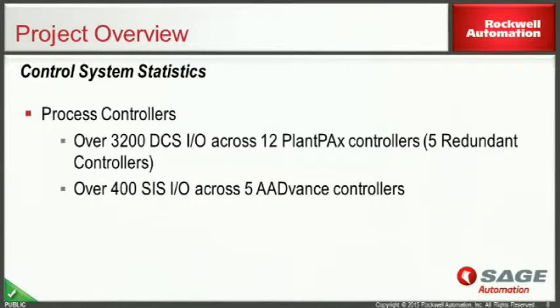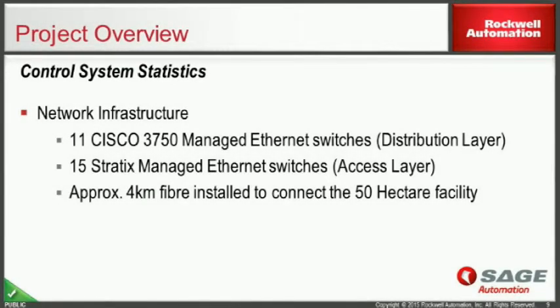So I'll go through a few of the control system stats. So the process controllers, there was over 3,200 DCS I/O across 12 PlantPAx PX controllers, and 5 of those controllers are redundant controllers. And the system consisted of over 400 safety I/O across 5 AADvance controllers. The new network infrastructure consisted of 11 Cisco 3750 managed switches at the distribution layer, forming a self-healing ring, which I'll show you a bit later on, and 15 Stratix managed Ethernet switches across the access layer. And we installed approximately 4 kilometres of fibre to connect the 50-hectare facility.